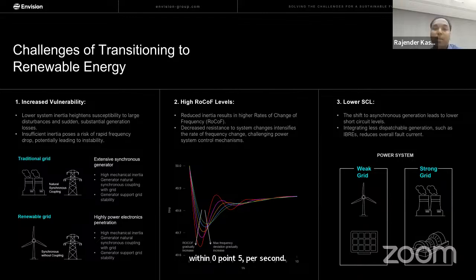Beyond inertia, one more parameter is that most renewable energy plants, like the solar PV inverters at the grid interface, are current controlled converters. When they are interconnected with the grid, this leads to a lower short circuit level. Current controlled converters typically rely on a phase locked loop control mechanism for system synchronization. It also refers to the fundamental component of the waveform for the voltage reference. So these are the basic drawbacks of conventional solar inverters.